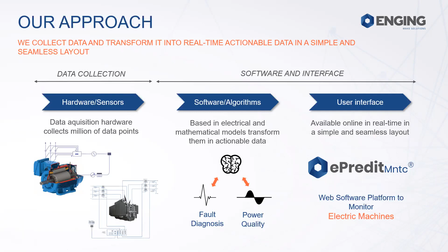So what are the solutions we've developed? We are very focused at this moment on transformers. We have three solutions: the TCM for power transformers with an on-load tap changer; low power transformers, which don't have the on-load tap changer because they are manual or fixed; and the OPTCM, a solution developed for nuclear power plants, for the emergency and auxiliary emergency power transformers. The other solution we've developed for industries is the MCM, the software for fault detection in electric motors.